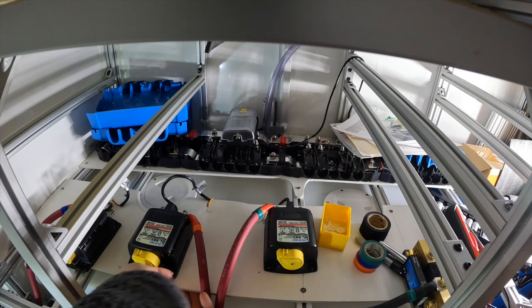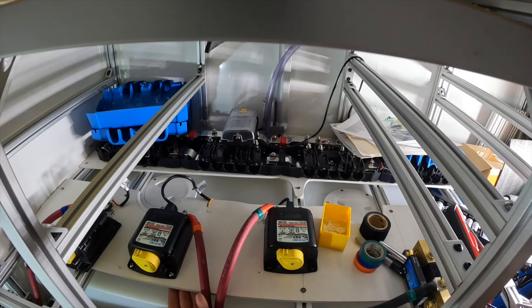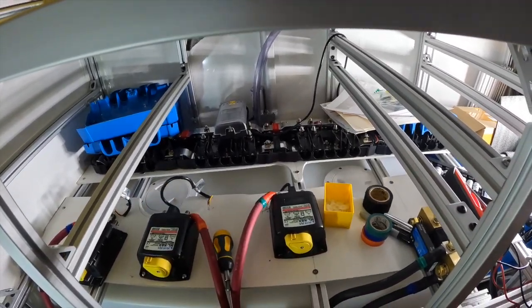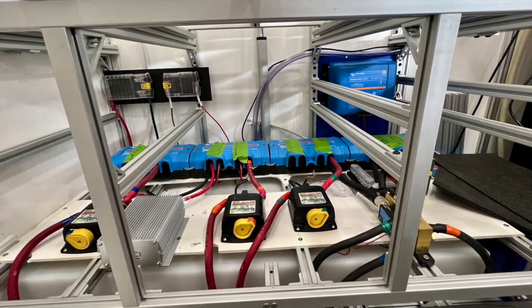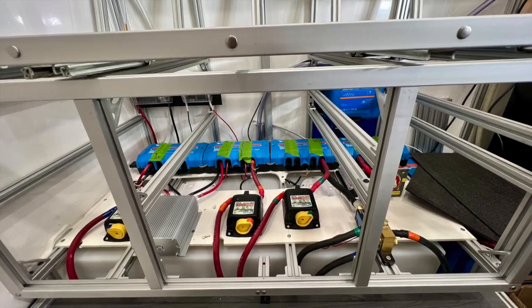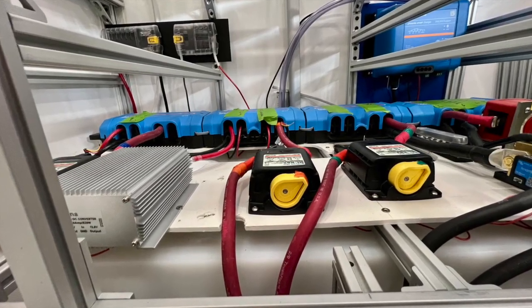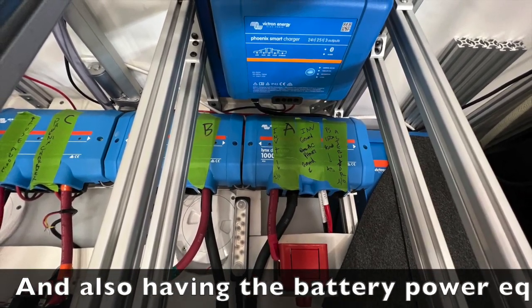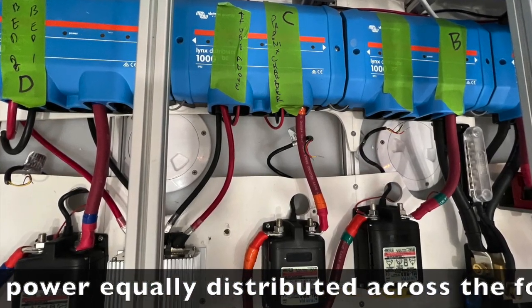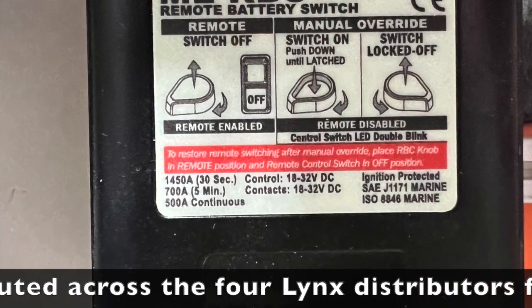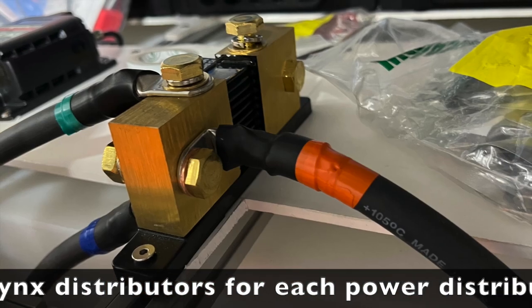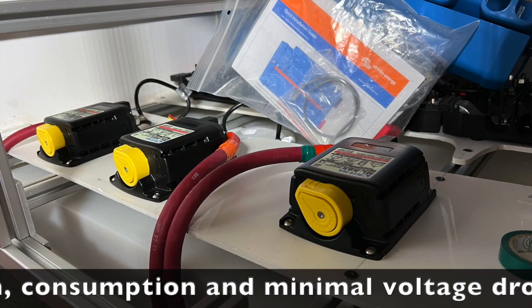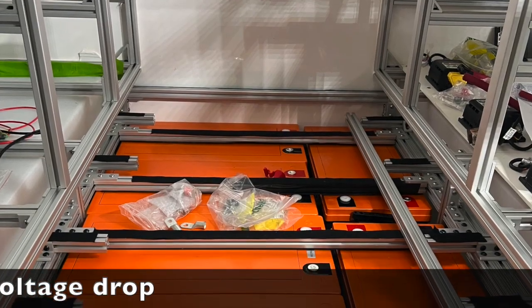This is what it looks like when they're all done, with all of them mounted up in a nice even row. All those cables go into the shunt so that each battery cable pair from each of the three battery pairs is exactly the same length going into the shunt, exactly the same length going into its RBS, and the same length going from the RBS into the Lynx Distributor. Then installing my shore power connection, which I'll talk more about in a future video, as well as finalizing the connections within the shunts, RBS's, and Lynx.